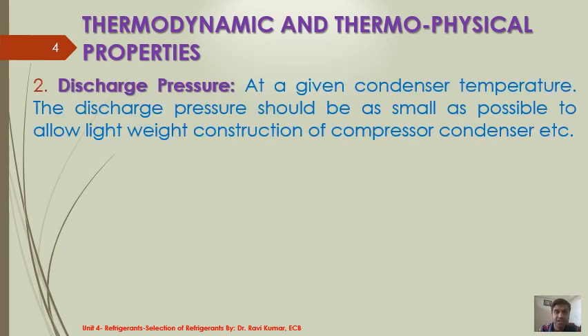The second point is discharge pressure. At a given condenser temperature, the discharge pressure should be as small as possible to allow lightweight construction of compressor, condenser, etc. When the maximum operating pressure is low, the tube thickness required for the condenser and the material chosen for compressors need not be heavy. That means you can go for thinner tubes, which reduces the cost and the weight of the system.